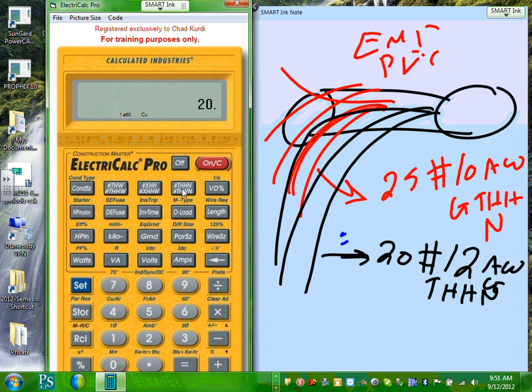What type of insulation? Chad used the same insulation. Otherwise, you can go to any of these insulations. Hit this one. So it'll give you the 20. Hit that again. It will give you the square inch for all these 20 conductors, number 12. And before that, we had the 25, number 10. Now you're done.